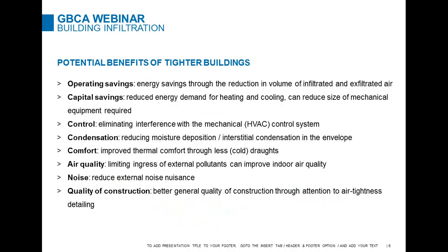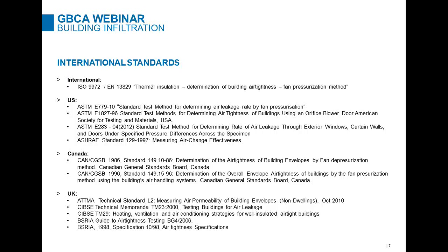Other potential benefits beyond those operating cost savings are capital savings associated with the reduced size of mechanical plant and equipment. If you've got a tighter building, you need less energy to cool it, and you need smaller pieces of plant and equipment to do that. You might improve the control and therefore your ability to maintain temperatures inside the building. You might have better control over condensation risk, interstitial in particular, improved comfort conditions for the people inside, and improved air quality, which potentially is particularly important in places like China now. Indoor air quality is a huge issue there. Noise, you'll have better acoustics, and the quality of construction will generally be improved by the better attention to detailing through the design process.